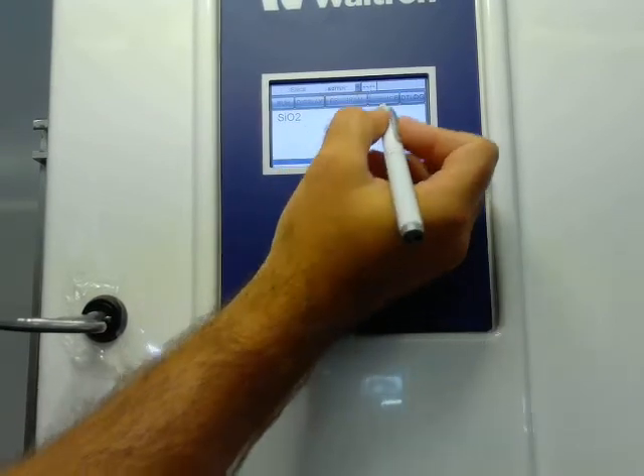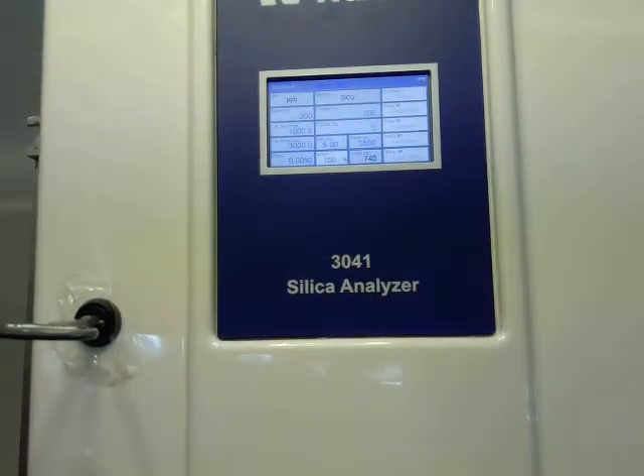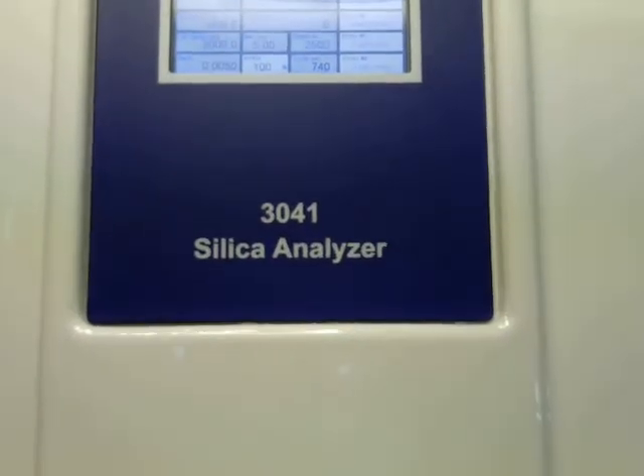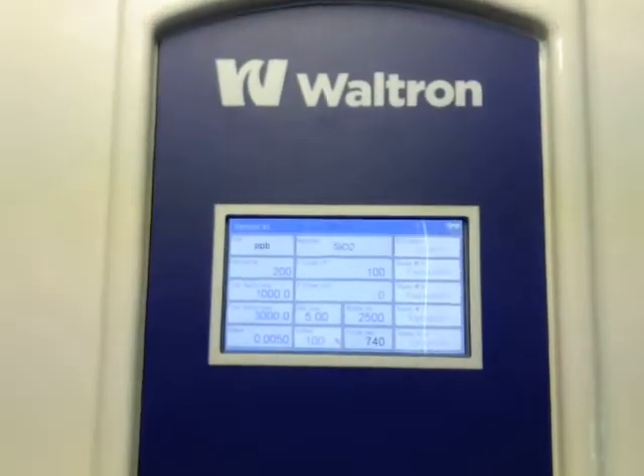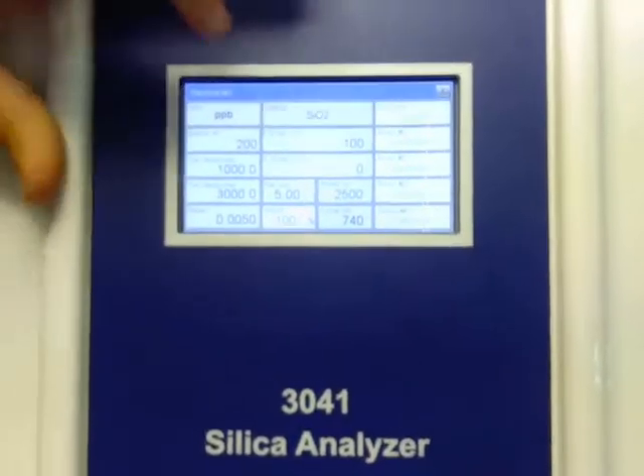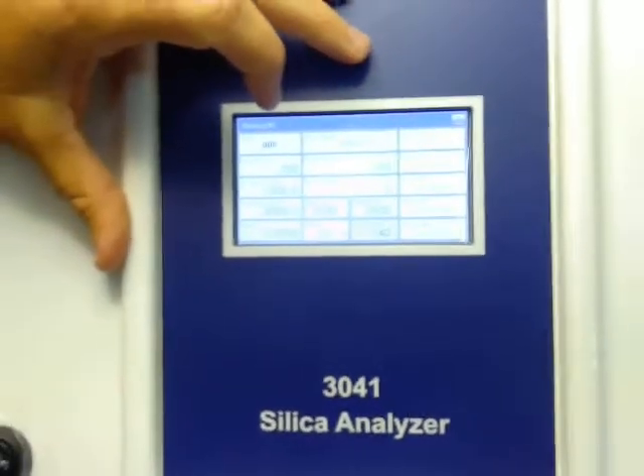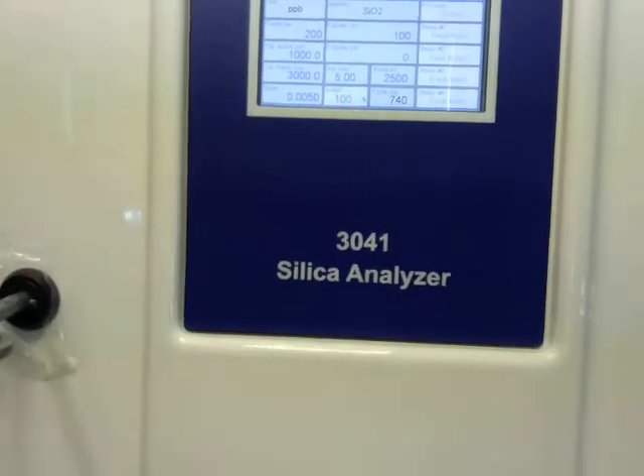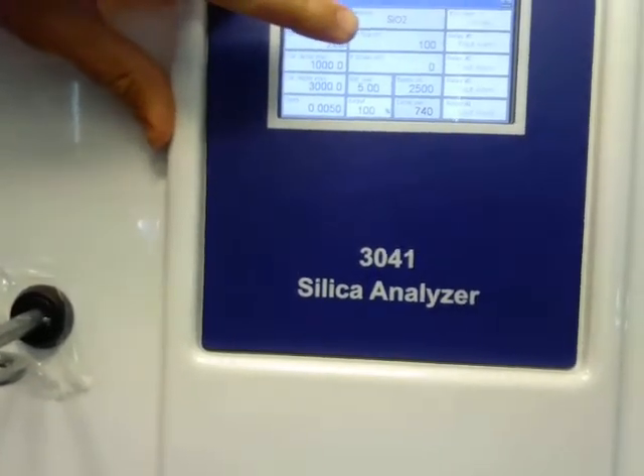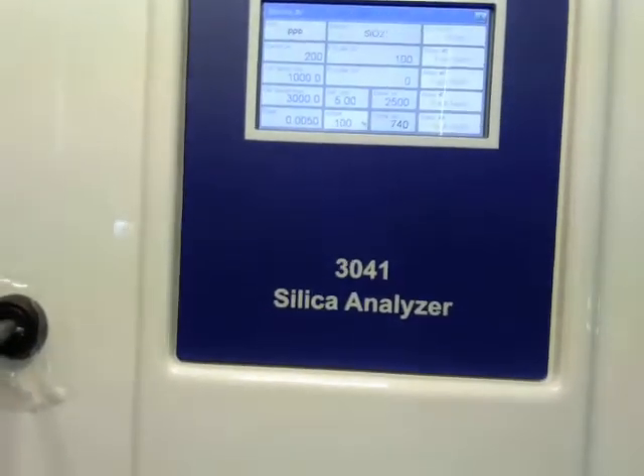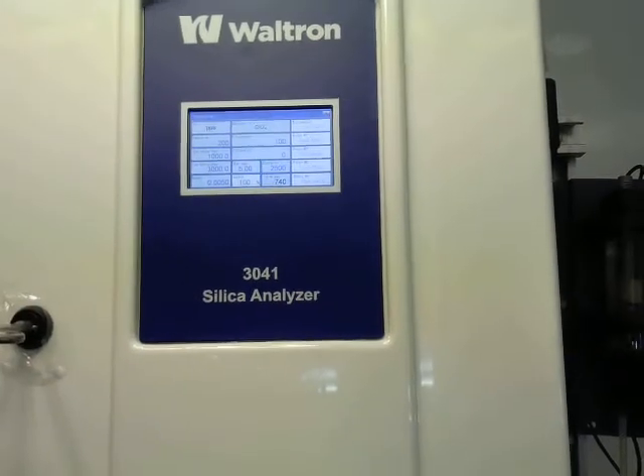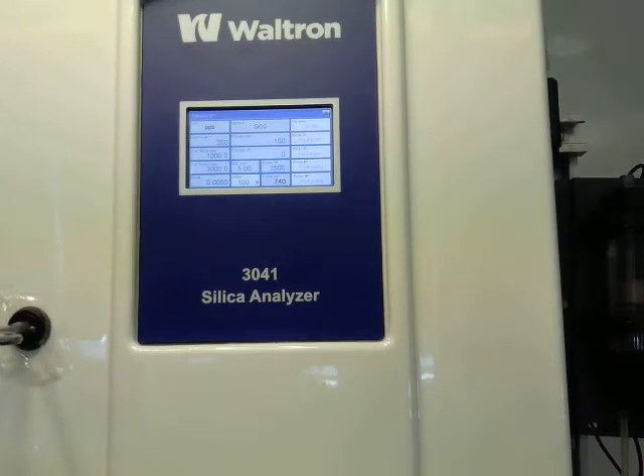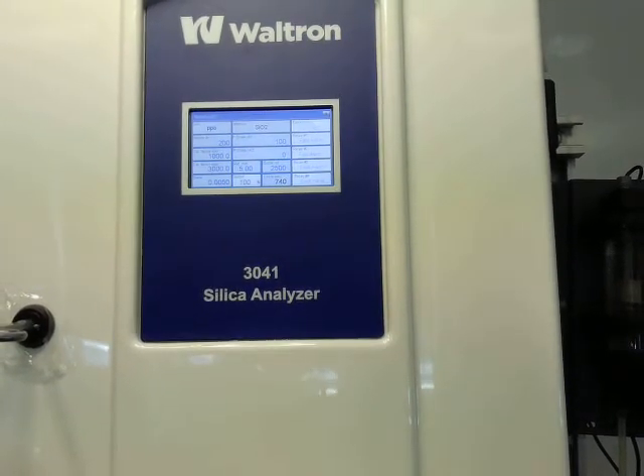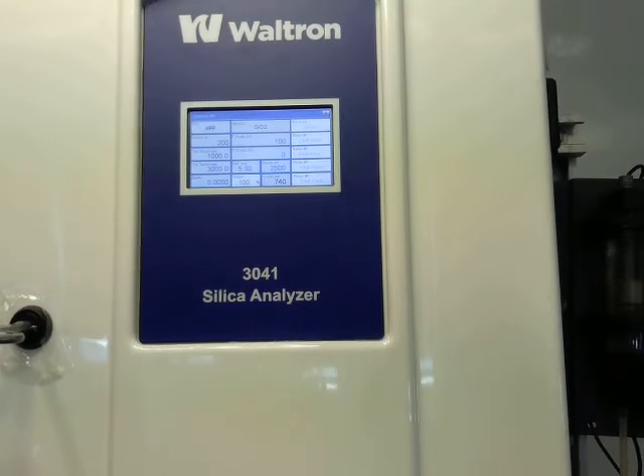I will show real quick, when you log in with the admin password, this service menu that you get access to. The main reason that you might need to come into this screen would be for this full scale number right here in the middle. And then obviously is the full scale of the analyzer, but what that also is tied to is your scaling for your 4 to 20 output. So your 4 is always 0, and then your 20 milliamps equal to whatever you put into this field. In this case, it's set to 100.